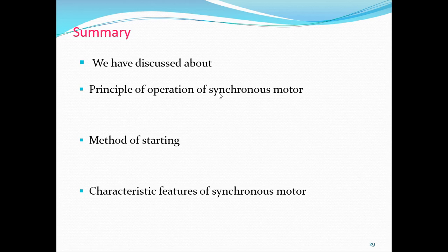So how can we make this self-starting? We have to connect the shaft with some external motor, that is a small DC motor or a pony motor. And when we rotate the shaft near to the synchronous speed, what happens? Automatically the rotor, which is mounted on the shaft, also starts rotating at synchronous speed. The rotor is rotating at synchronous speed, and the stator magnetic poles are also rotating at synchronous speed.